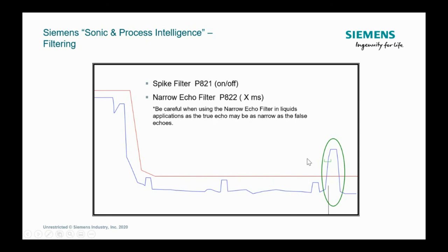You got to be a little careful for the water guys, especially when you use the narrow echo filter, insofar as water typically gives you a very narrow echo to begin with, and if you're not careful, you can actually take out the very signal that you were trying to measure. And so, don't be real aggressive with that, especially if you're measuring water or some liquids.